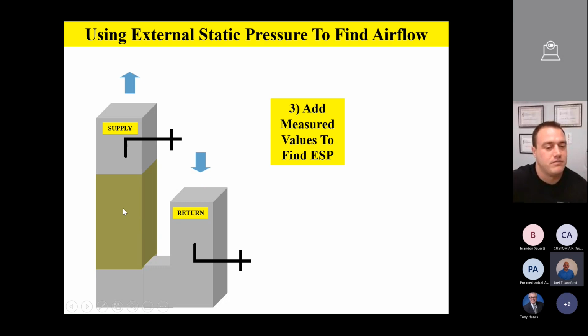Guys, you got to remember, on an air handler, you're gonna have your fan. Your coil will actually be in the air handler. Yeah, the coil's on the bottom, fan's on the top, most units. Okay, and that's fine. So what you're gonna do, you're gonna take two readings. Poke a hole so that you're reading just the fan, and then poke another hole above the coil so that you can see how much static pressure drop you got across the coil, if that makes sense.